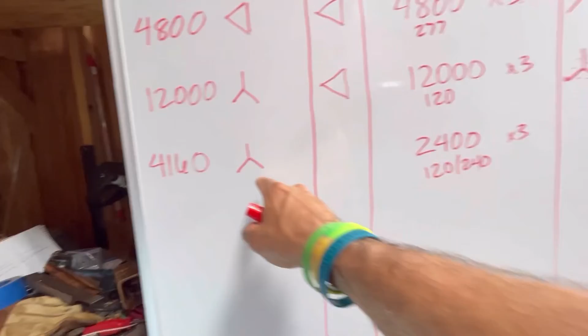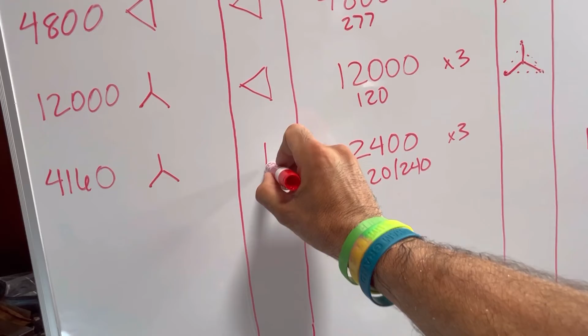Right on. So in the last one, 4160Y, let's say the nameplate just says 2400, 120/240. Customer needs, let's say, 120/240, 3-phase, 4-wire. So again, 3 transformers here. So 4160, 2400. Do these numbers match? If they don't match, it's going to be a Y. Where does 2400 volts live on this circuit? It's going to be phase to neutral, right? So this is going to be a Y primary hookup.